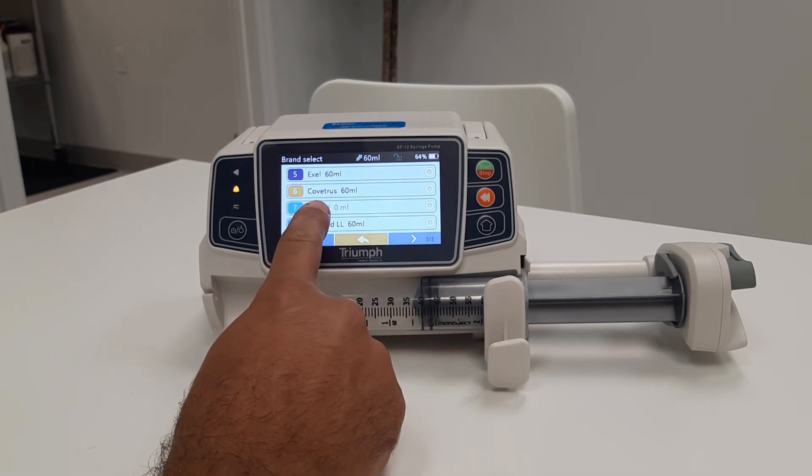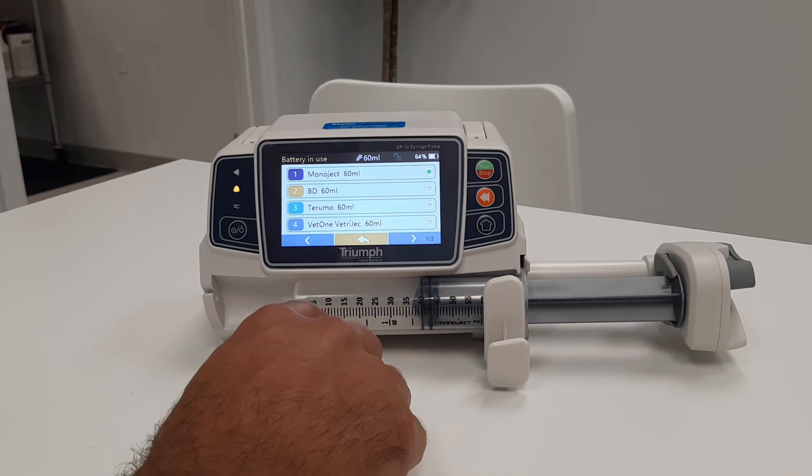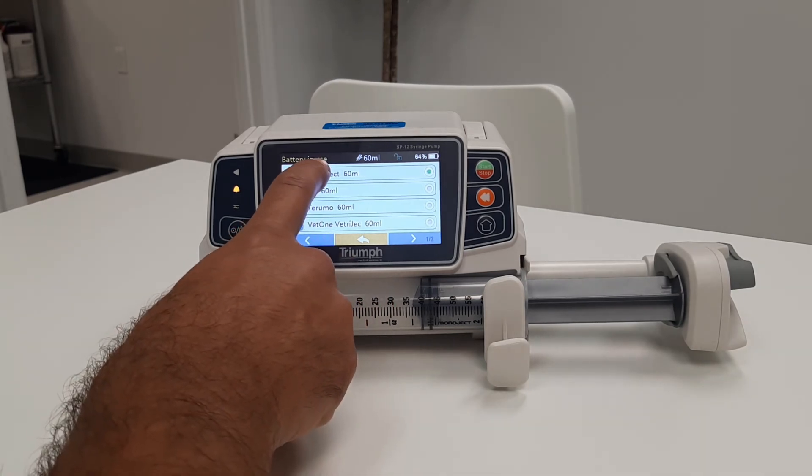Notice some manufacturers are grayed out. This is either because the plunger is too short and is not accepted by the pump, or the manufacturer does not simply make that size of syringe. In this case, we'll verify that we're using a Monoject 60.